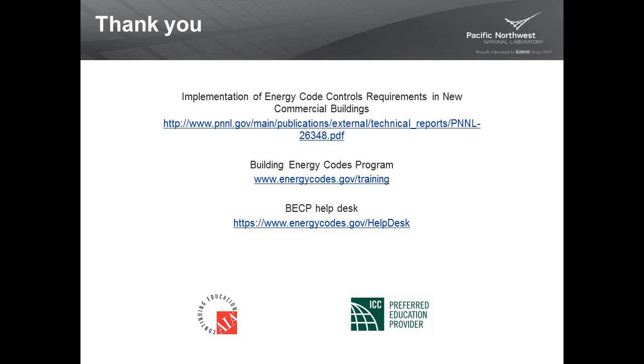The other thing in codes is, the issue of capable versus configured is a little bit tricky. In some instances, the code says things should be capable of doing something. In other instances, it should be configured. We took it to mean, we interpreted this for this study, that while the codes do not require long-term operational parameters of the building, the controls should be configured according to the code as it's turned over to the AHJ and the building gets a certificate of occupancy. So that's an interpretation that we made that we think is correct.